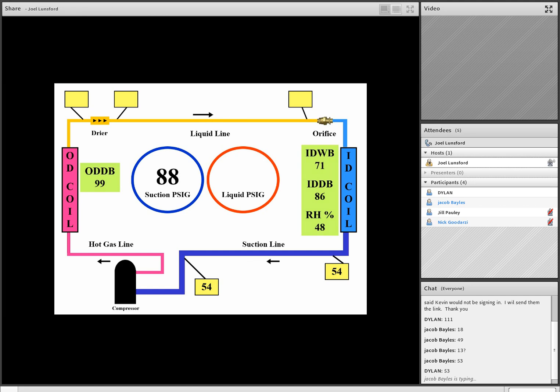Good diagnosis. Any questions or comments on that? Okay, well, let's do a couple more just to make sure everybody's got this. In this next example, we have 132 pounds of suction pressure, and this is on a 410A unit because we have pink colored background on the gauges. Now, we do have an expansion valve, a TXV, so an expansion valve should maintain a superheat of about 10 to 15 degrees. So we automatically know we're looking for a range of about 10 to 15 with the expansion valve. So somebody help me out on the R410A pressure temperature chart, at 132 pounds of pressure.